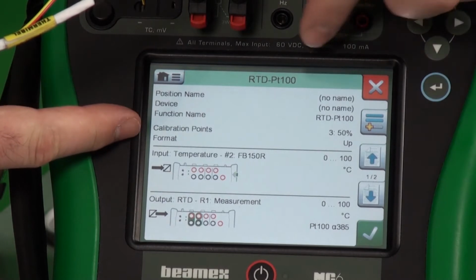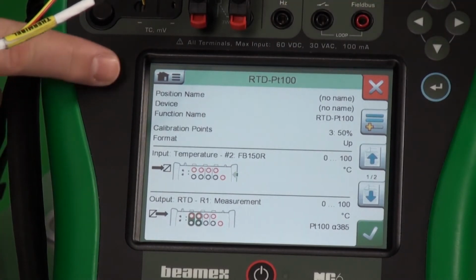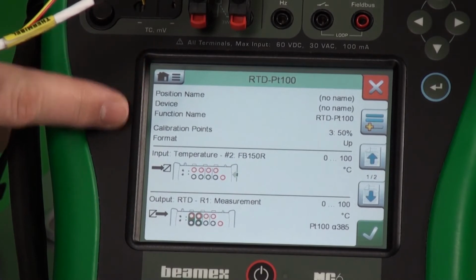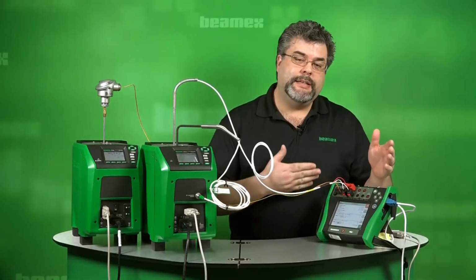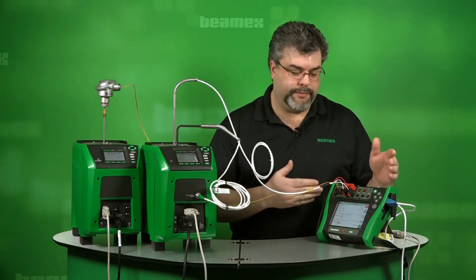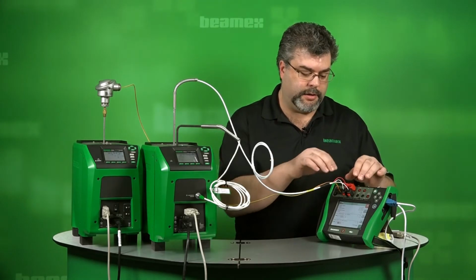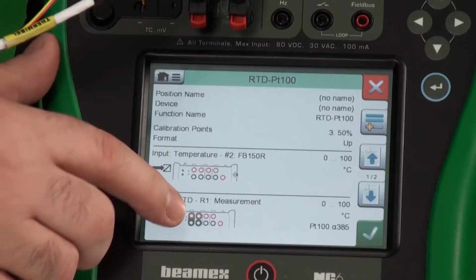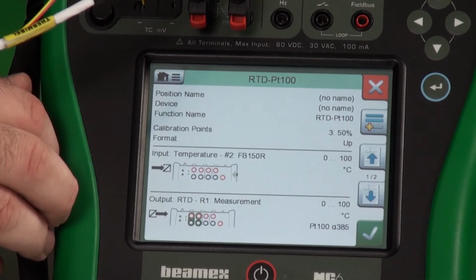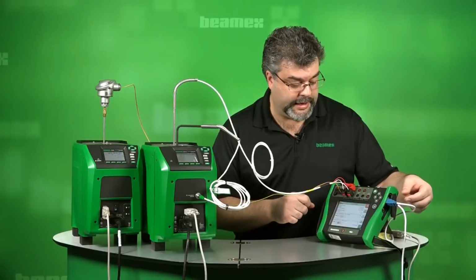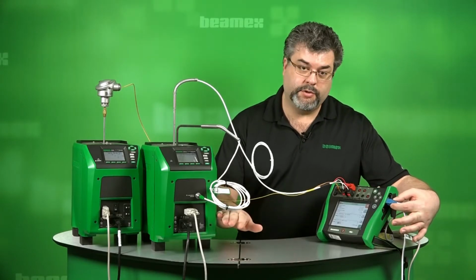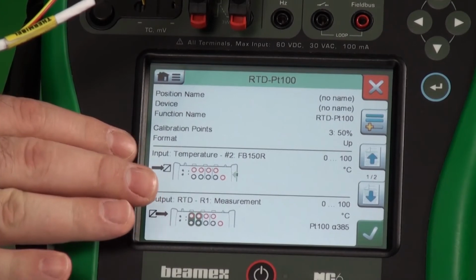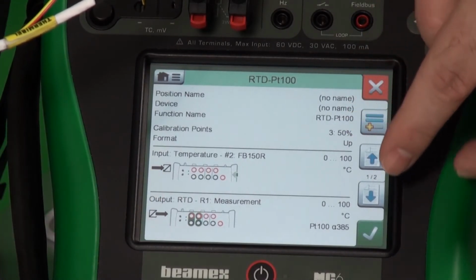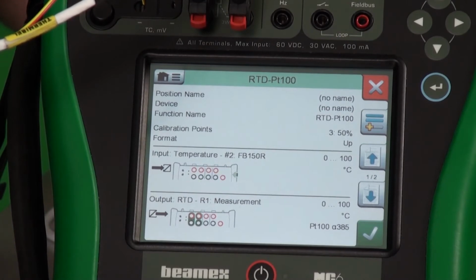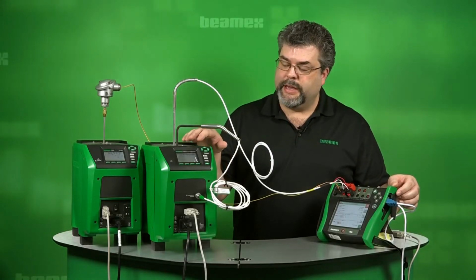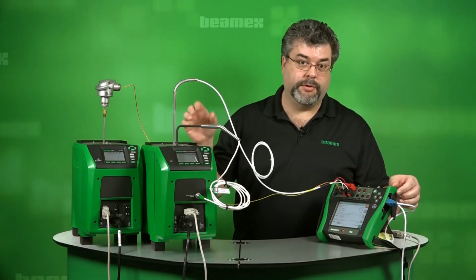Our first test, it says right here, is our RTD. It tells us our position name, it tells us our function name, it tells us our input. And not just the input, but where to connect. If I was new at this, and maybe I didn't know that the RTD needed to be connected right here, it shows me right here on the bottom. For the input, it shows me right here that I need to be connected to my USB port to control the dry block. My input here is 0 to 100 degrees Celsius, and my output is 0 to 100 degrees Celsius. We're actually testing the temperature element. We're proving that at 0 degrees C, it's actually outputting 0 degrees C.